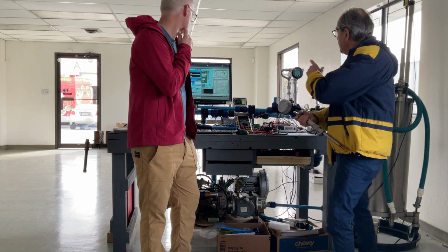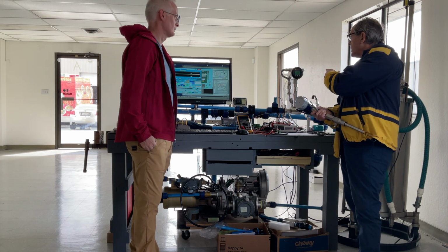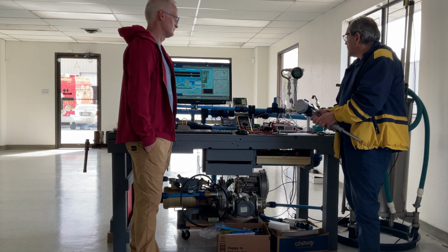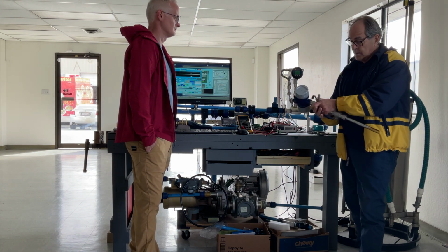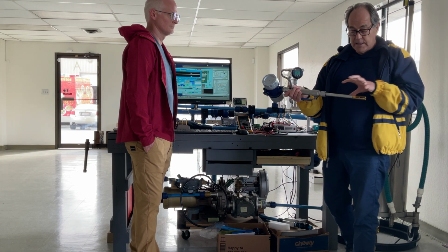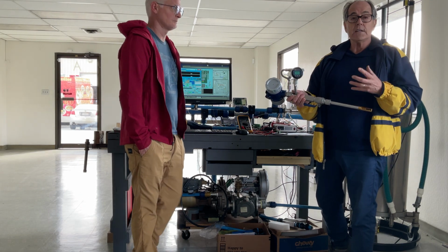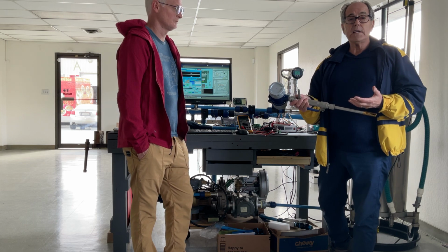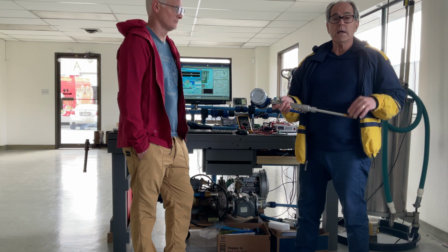As well, the vortex meter has enjoyed similar advances in electronics. The vortex meter's Achilles heel is vibration. The thermal mass flow meter's Achilles heel is temperature. This thing doesn't really like changes in temperature or gas composition. Temperature can be compensated, but typically most of the companies who make these don't do it properly.